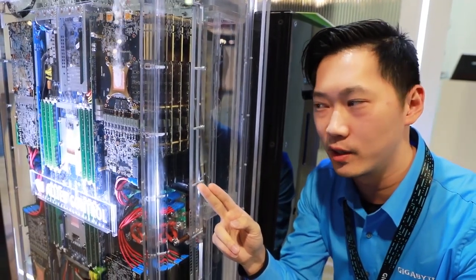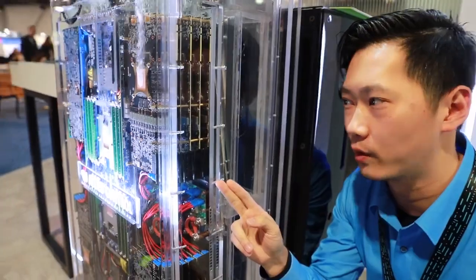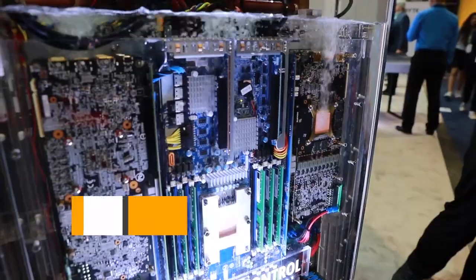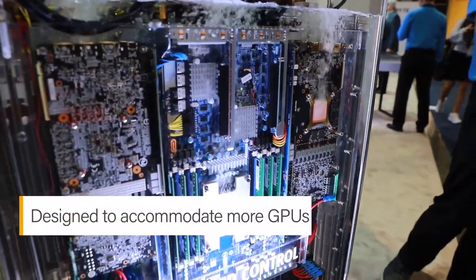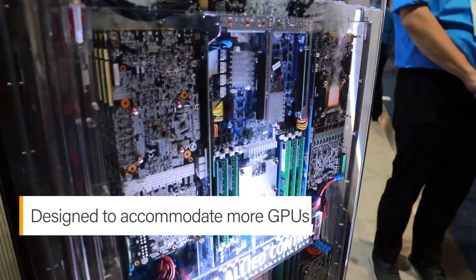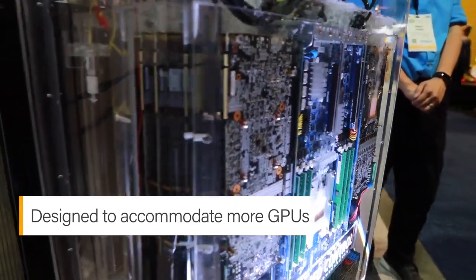Looking from the side, you can see this unit is totally compatible with our 2U high server. We replaced the CPU and GPU heatsinks with a thin copper foil that is more suitable for heat transfer in liquid. We also increased the capacity to accommodate 16 full-high full-length accelerators, which is double the previous generation.